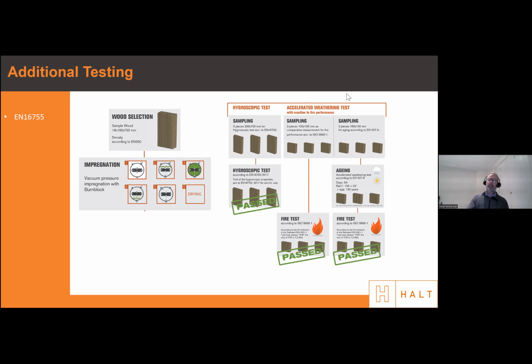So we can do additional testing. We can test everything to the standard for reaction to fire, but there are other tests out there that will help verify the benefits of impregnated timber used in construction. We can test it as a through and through process by doing the cone test, and then we can take it a step further and test it against 16755 for durability. So we can prove and demonstrate that the fire retardant will not leach from that timber over time. It's as good at the start of the test as it is at the end of the test. Therefore, we can declare that it's ideally suitable for exterior use.